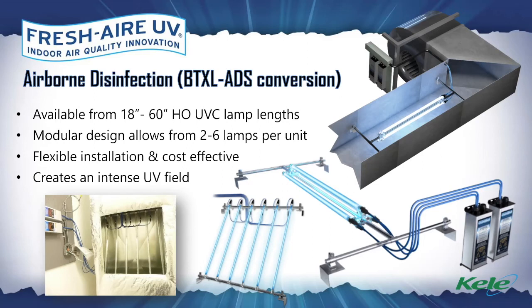lamps. And if we are doing a very large system or very, very fast velocities, we could use multiple ADS systems. But the concept of the ADS is that you want to deliver the necessary UV dosage, allowing for that dwell time. And as the air is passing through the ductwork, it reaches that UV field with the parallel orientation to airflow. And as the air enters that UV field, you're able to address the air as the air is being sterilized by the UVC light.